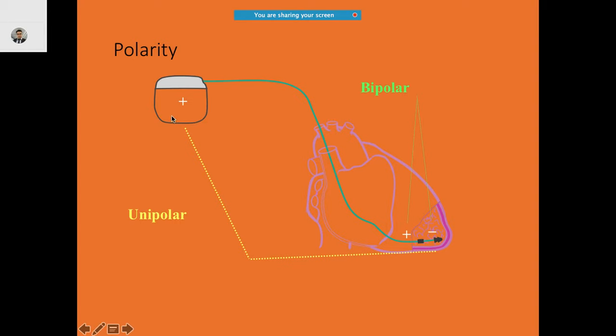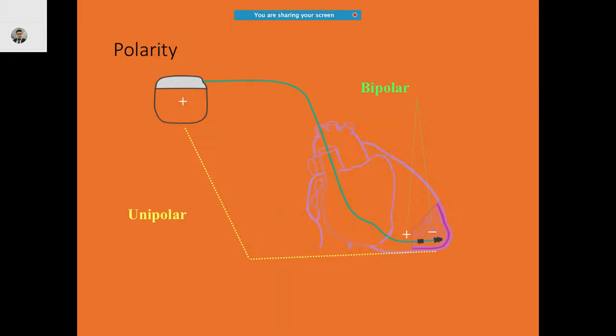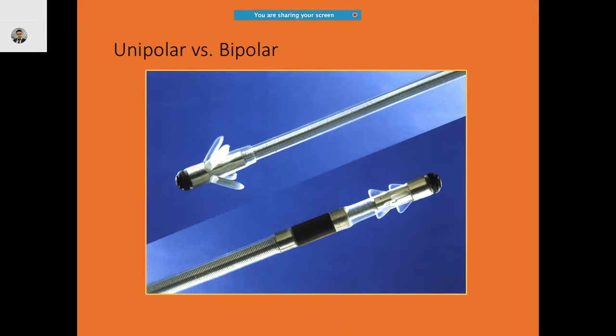For unipolar, the direct flow is unidirectional between the lead tip and the can. For bipolar, it makes a circuit — negative to positive. Unipolar needs only one pole for operation; the flow is always negative to positive. For bipolar, there are two poles, and the current flows from negative to positive to complete the circuit. The lead design is also slightly different from unipolar.